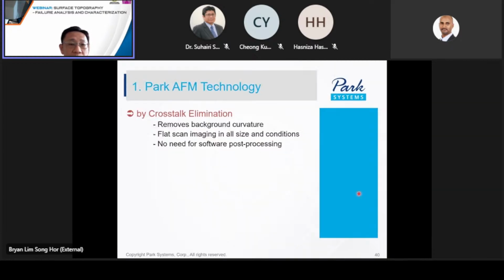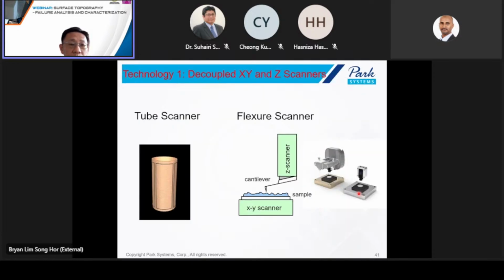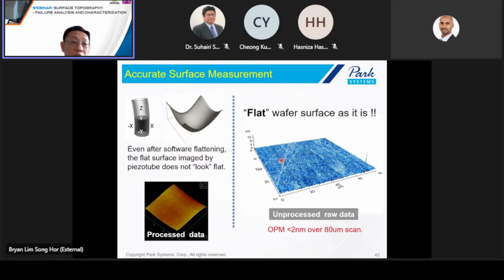So some of this technology, which I'm going to talk about, is crosstalk elimination. As you know, most AFMs use a tube scanner where there's X, Y and Z direction piezo. Okay, but this is not the best AFM. So Park Systems comes out with a flexure scanner which decouples the Z and XY. So instead of the X, Y and Z being together, they are decoupled separately. Okay, and this results in very accurate surface measurements, right?